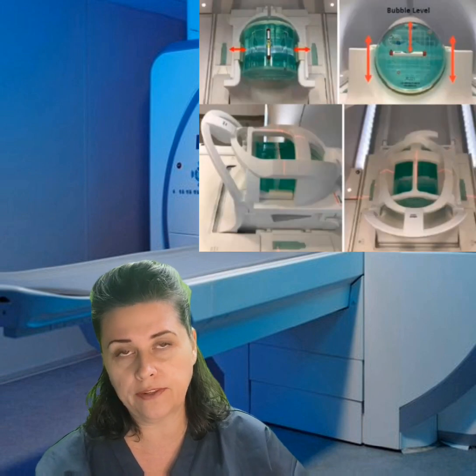ACR Phantom is cylindrical. It has two writings on it. They say nose and chin. Those writings are for positioning, and usually the phantom is positioned into the head coil. We use the bubble level to make sure that the positioning inside the coil is right. The color of the phantom is a tint greenish color. It contains two things: sodium chloride and nickel chloride.